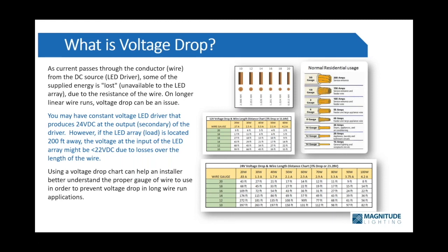If you look to your right, you see some diagrams here to give you an idea. So if you're working on a project and you have to figure out what type of wire gauge, what wattage of driver you need based on the actual footage — if you're working with a 24 volt constant voltage driver and you need to reach 130 feet, you can see here you would recommend using a 12 gauge wire at 40 watts. So you would need a driver at least 40 watts. That allows you to have consistent power performance of the driver as well as your light source. These are handy things, and they can be found on our website, or just by a general search on the websites.